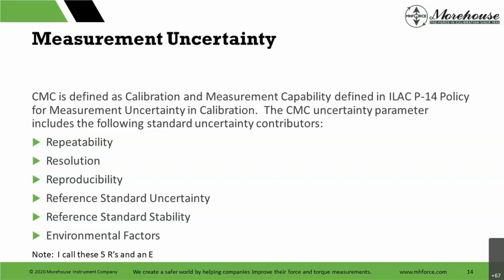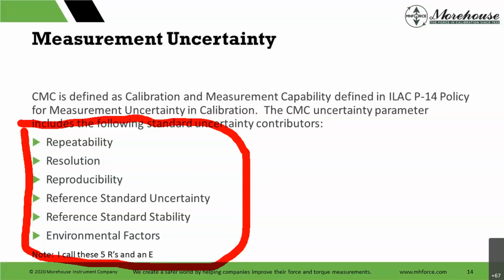Anyway, I digress. The next ones, so it's the 5 R's and an E: reproducibility, reference standard uncertainty, reference standard stability, environmental factors, and there's another one that I throw out there, and it's just other. And other is your catch-all, right? That's where you can throw things like some specifications from load cells. You can throw some other things. What we don't want to see happen here for the general masses that are doing this is an accuracy spec negating all of this good metrologically sound advice. We don't want to see an accuracy spec used in lieu of all this. You need to do the testing.